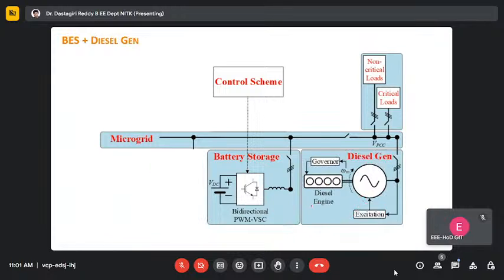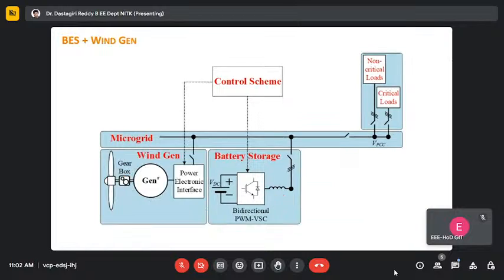Now, if the diesel generator comes into the picture, what's the problem? The diesel generator can take care of voltage and frequency, and the converter can go into PQ mode, but there are some problems we'll discuss shortly. So when the diesel generator is present, it maintains voltage and frequency, and the voltage source converter goes into grid-following mode, in PQ control.